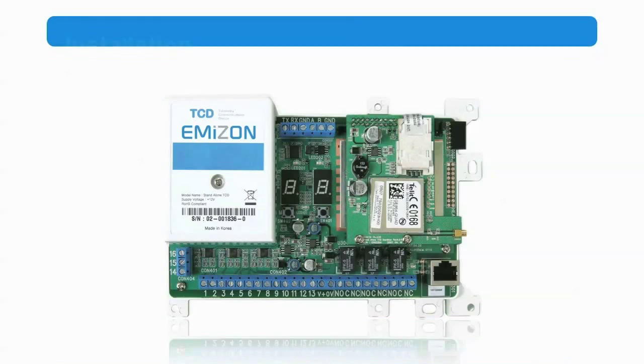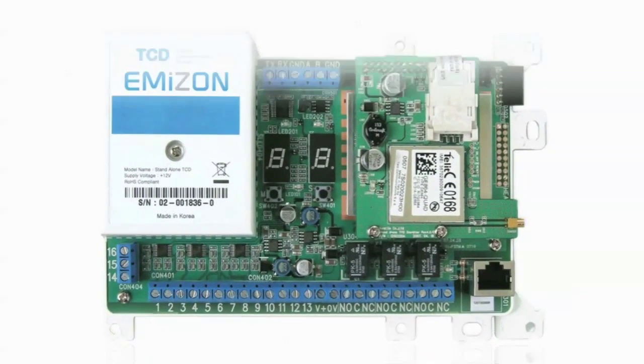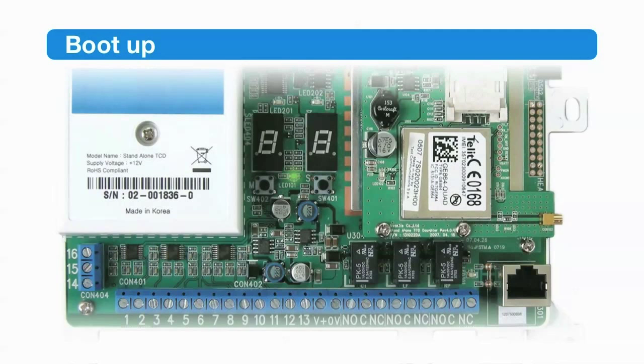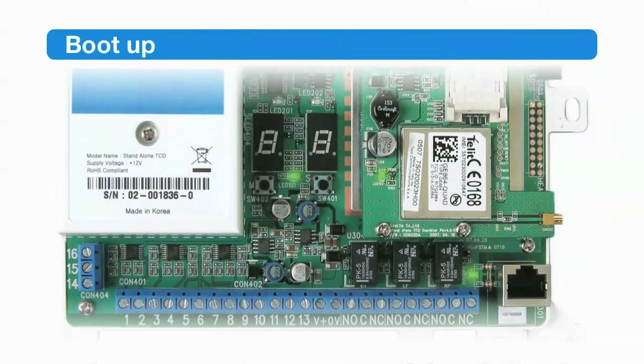Install complete — turn on the power. The boot up process takes about 30 seconds, with success indicated by a solid light on the power status LED, a flickering light on the ethernet activity LED, and a flashing green light on the GPRS activity LED. The display will run through the sequence BU for boot up, BC for boot complete, and then TI for TCD initial state. Once you see TI, you're ready for the next stage.